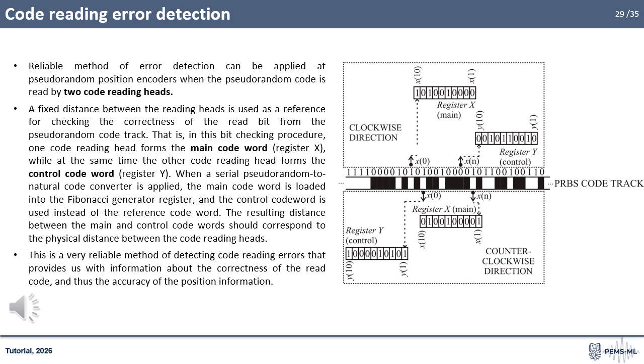A reliable method of error detection can be applied at pseudorandom position encoders when the pseudorandom code is read by 2 code reading heads. A fixed distance between the reading heads is used as a reference for checking the correctness of the read bit from the pseudorandom code track. That is, in this bit checking procedure, one code reading head forms the main code word, register X, while at the same time the other code reading head forms the control code word, register Y.